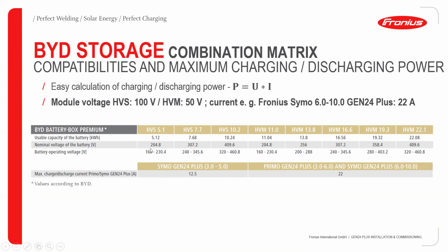in this case, two modules of HVS, which come at a nominal voltage of about 100 volts, this gives you up to about 200 volts. And if you have 4 of them, it will give you up to 400 volts, or exactly 409.6 volts. So that is 100 times 4. And from the previous slide, I told you can have up to 8 stacks of the HVM module. These are 50 volts rated. So 50 times 8 gives you approximately 400, so it will give you exactly 409.6 volts also, same as for the HVS.